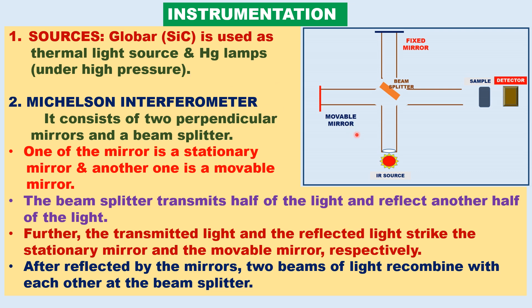The mercury vapor under high pressure also serves as a source. The instrument consists of a Michelson interferometer. This setup is called the Michelson interferometer. It consists of two mirrors: a fixed mirror and a movable mirror, as well as a beam splitter.